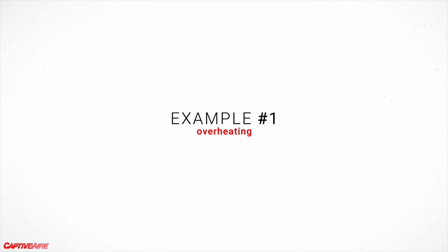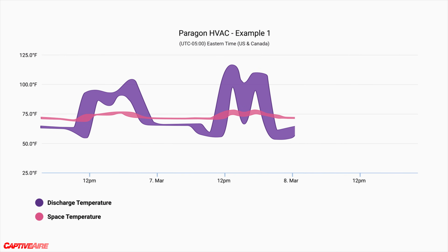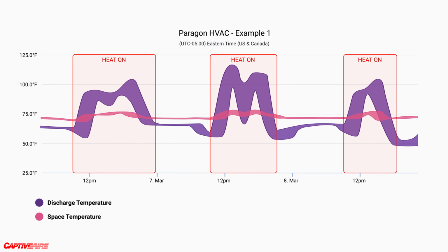We had a site where they were complaining that the space was overheating, but then it would get back to temperature. It was only while the heat was running that the space would overheat. And when we pulled back the historical CASLink data, what we found is whenever the heat would kick on, the discharge temps would be much higher than expected.